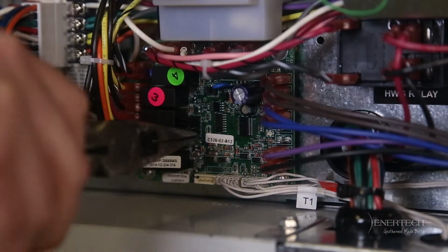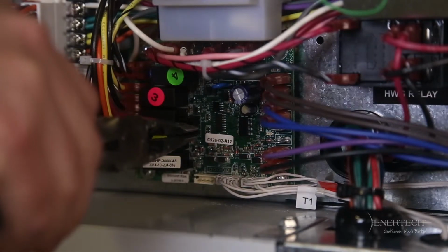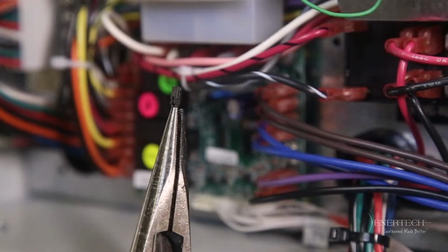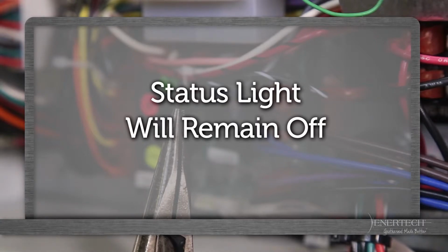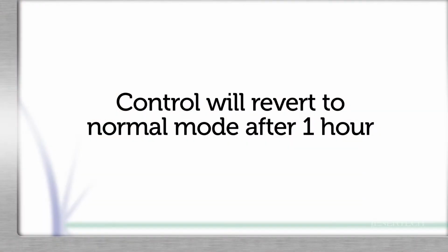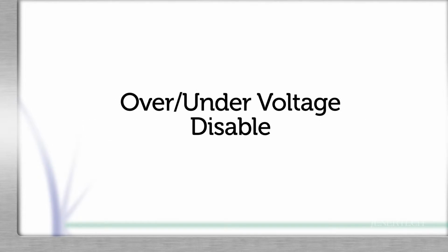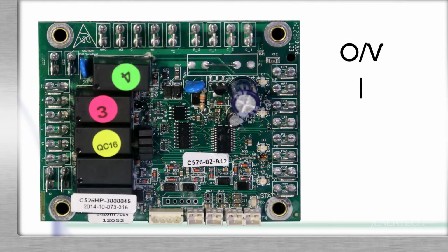When service is complete, the jumper must be reinstalled in order to make sure the unit operates with normal sequencing delays. While the test jumper is removed, the status light, bottom green, will remain off. If the test jumper is not reinstalled, the control will revert to normal mode after 1 hour, green status light blinking. When the over-under jumper, or the O/V jumper, is installed, the over-under voltage feature is active. When the jumper is removed, the over-under voltage feature is disabled.